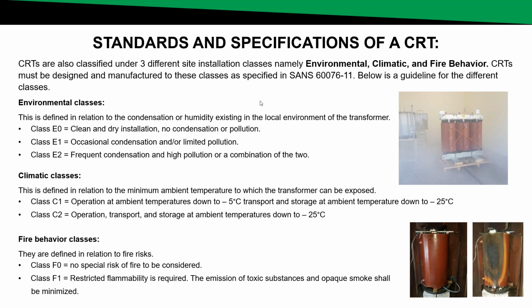Class E1, occasional condensation or limited pollution. For E1, this is typically an outdoor installation where the transformer is installed outdoors, where medium condensation can occur, and the transformer is exposed to just a little bit of pollution. Class E2 is frequent condensation and high pollution, or a combination of the two. This is usually an outdoor installation where the transformer is exposed to very humid conditions and a lot of industrial pollution is around the environment of the transformer.